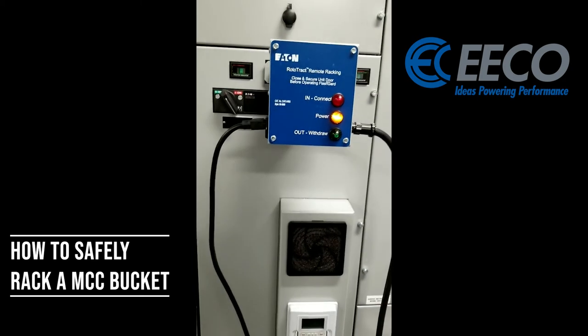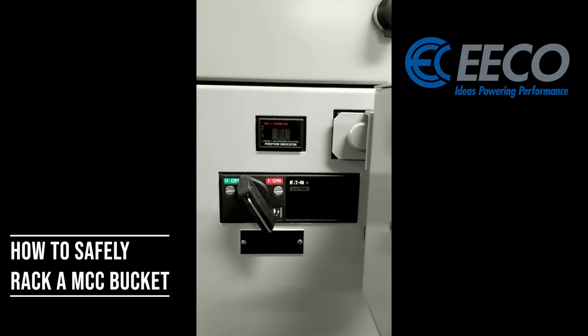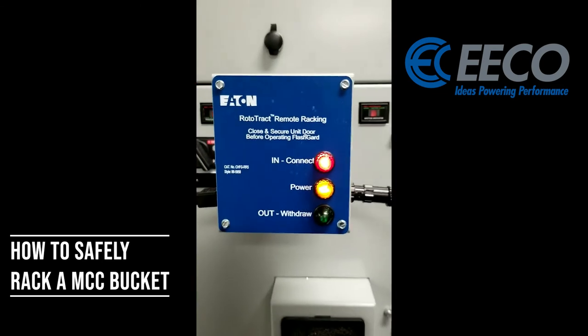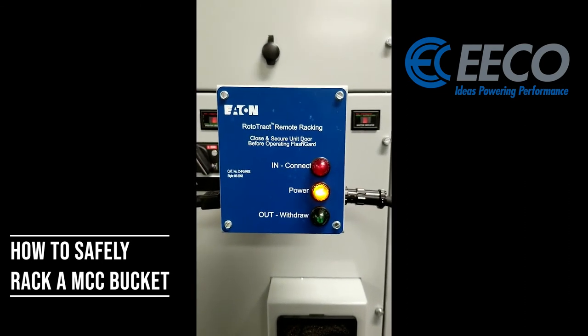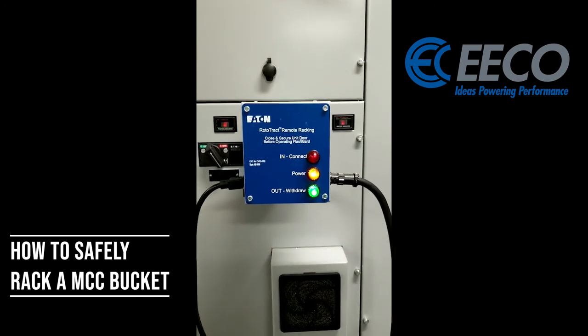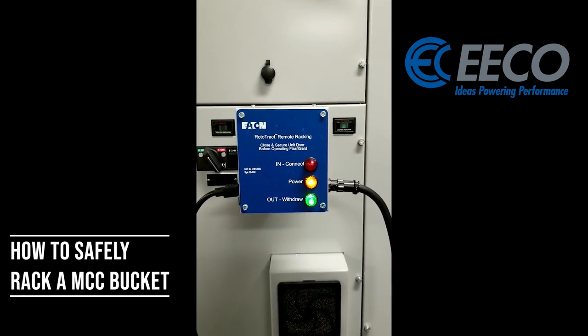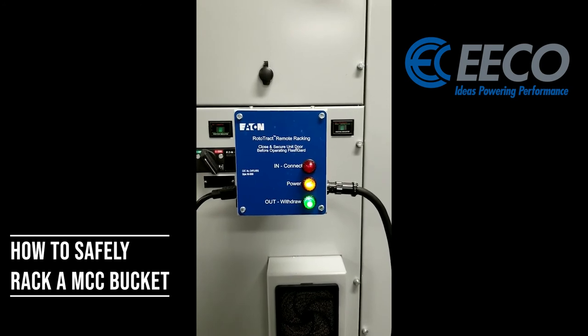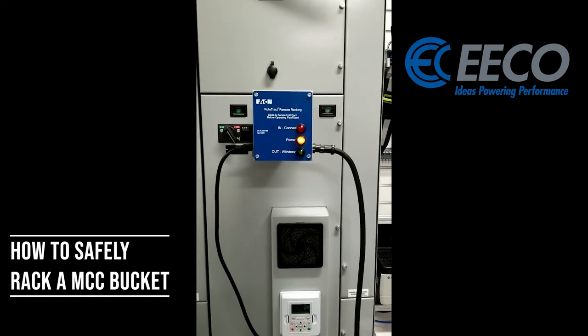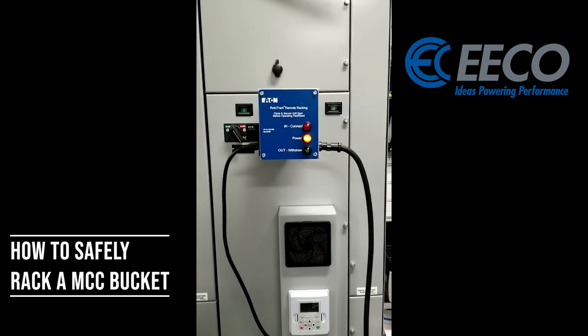I'm going to go ahead and rack this in — I've got it screwed in all the way. I hit in and you'll notice right away my shutters change. They went from green to black as it's traveling, and now they're red — that means it's connected. You can hear it clicking, and again that's what we talked about with not being able to over-torque it. Now I'm going to go back out: they change from red to black on one side, then both go green. You can hear it clicking so I can't over-rack it. That's the Eaton RotoTract remote racking device — or you can use your drill with the socket adapter, whichever works best for you. That's how you rack in and out a bucket all without having to turn power off on the MCC.